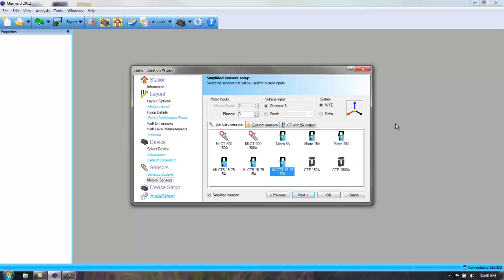Now depending on the station and the size of the motors that you're monitoring, you want to select your current clamps accordingly. For small motors, 15 horse, 20 horse and below, I usually use the 75 amp current clamps. If I get above about 30 to 40 horsepower, I go with 150 or 300 amp clamps. This is primarily because the clamps will read down to 5% of its rated value. So a 300 amp clamp will read down to a 15 amp input. If it's below 15 amp, we won't record it.